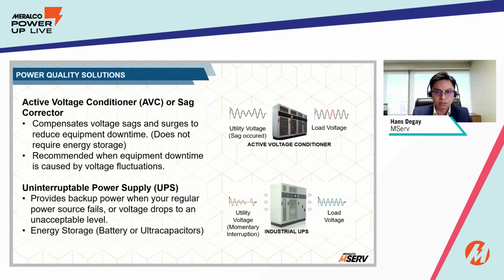On the other hand, UPS have energy storage. UPS of data centers usually make use of battery energy storage as they are designed for long duration but not outright power such as motors. This is where UPS with ultracapacitors takes place if it's an outburst of power such as motor loads, and not really designed for long duration interruptions, just for protecting the equipment from fluctuation so that there is time to shut down the equipment.